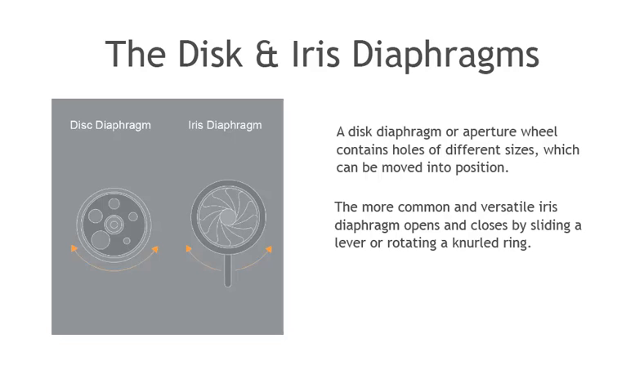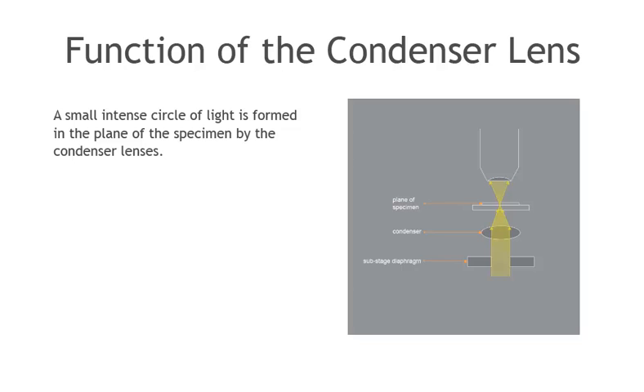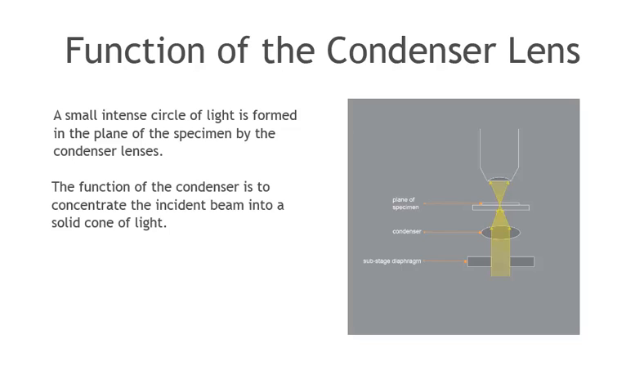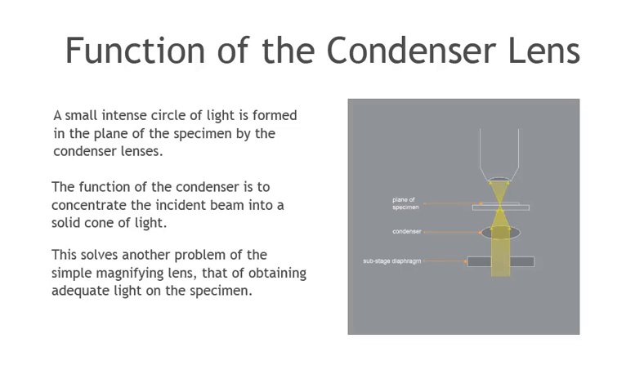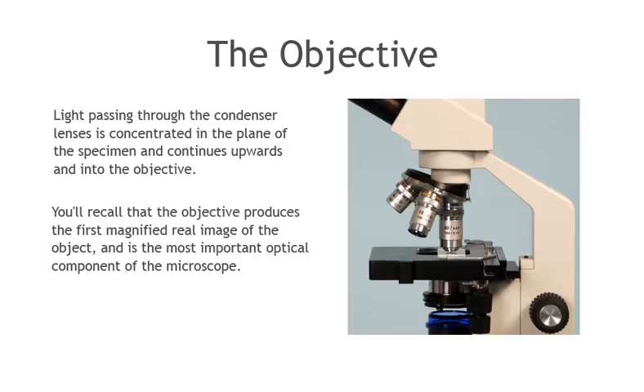The more common and versatile iris diaphragm opens and closes by sliding a lever or rotating a knurled ring. A small, intense circle of light is formed in the plane of the specimen by the condenser lenses. The function of the condenser is to concentrate the incident beam into a solid cone of light, which solves another problem of the simple magnifying lens — that of obtaining adequate light on the specimen. Light passing through the condenser lenses is concentrated in the plane of the specimen and continues upward and into the objective. The objective produces the first magnified real image of the object, and is the most important optical component of the microscope.